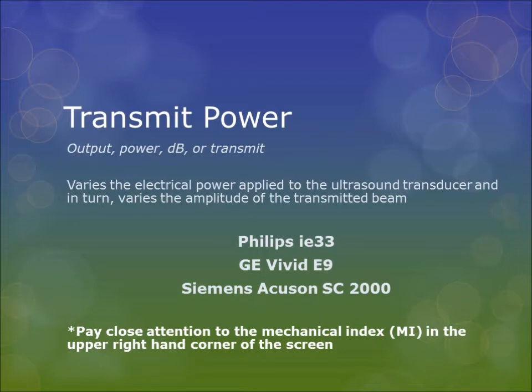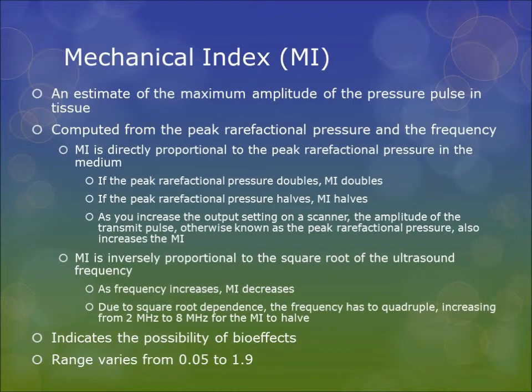Please pay close attention to the mechanical index, or MI, in the upper right-hand corner of the screen. Mechanical index is an estimate of the maximum amplitude of the pressure pulse in tissue. MI is computed from the peak rarefactional pressure and the frequency. MI is directly proportional to the peak rarefactional pressure in the medium — if the peak rarefactional pressure doubles, MI doubles; if it halves, MI halves. As you increase the output setting on a scanner, the amplitude of the transmit pulse (the peak rarefactional pressure) also increases the MI.